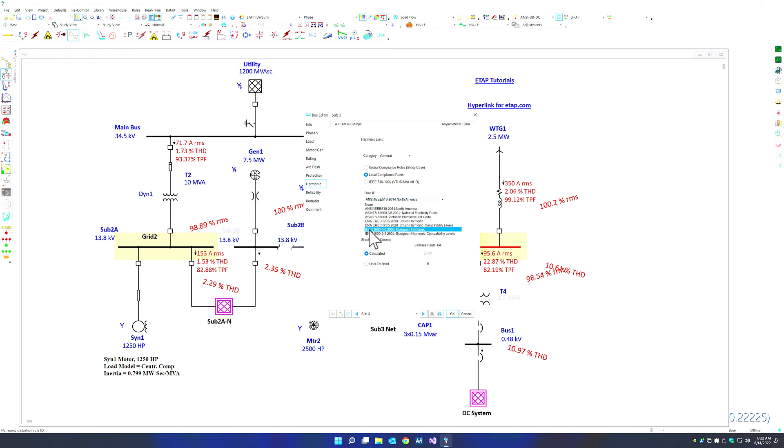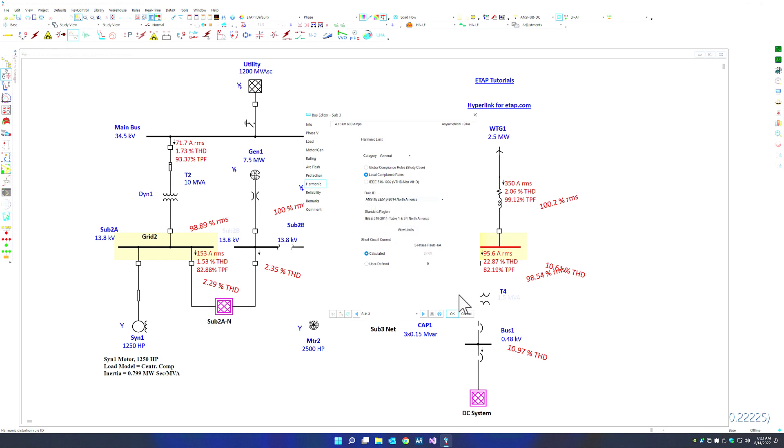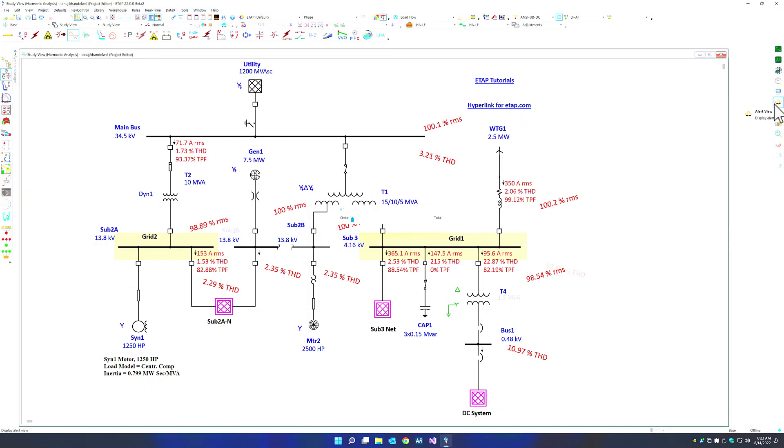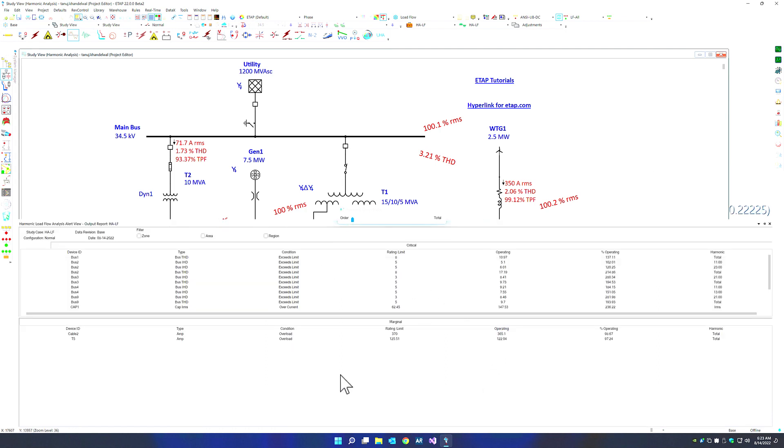You can pick from these different emission rules and use those within the program such that we can get our assessment of the harmonic limits that are being generated in the system and compare them versus these rules. Any issues or violations based on these rules are then graphically shown in the ETAP program in the alert view. The alert view is a very good way to let us know that we are exceeding the total harmonic distortion or the individual harmonic distortion or both within this electrical system.